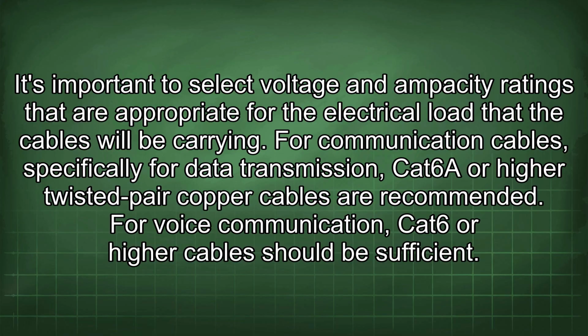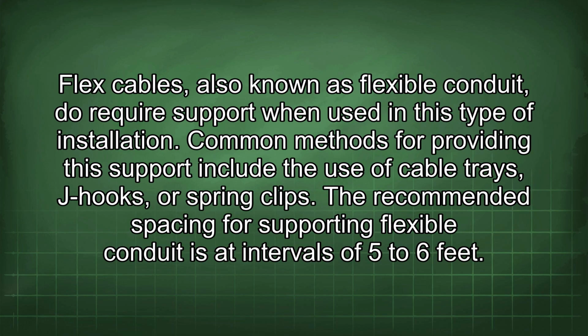carrying. For communication cables, specifically for data transmission, Cat6A or higher twisted pair copper cables are recommended. For voice communication, Cat6 or higher cables should be sufficient. Flex cables, also known as flexible conduit, do require support when used in this type of installation. Common methods for providing this support include the use of cable trays, J-hooks, or spring clips. The recommended spacing for supporting flexible conduit is at intervals of 5 to 6 feet.